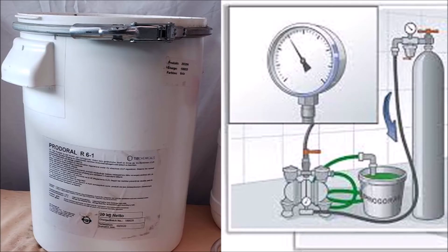We have two types of Prodoral. Prodoral H is used for sealing piping used for heating, like radiators. And Prodoral R6-1 is used for sealing the inside of gas pipes. In this video I'm going to talk about Prodoral R6-1, which we use for sealing leaks in gas piping, especially in home gas. Prodoral R6-1 is a plastic material that has a viscosity similar to very thick paint.